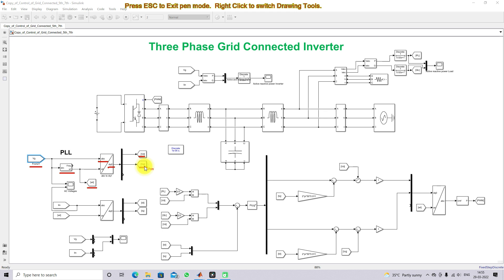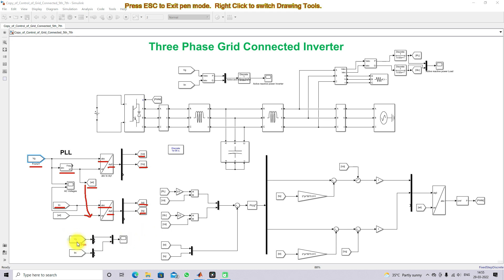Here we are controlling the inverter current. The inverter current is converted into DQ form using ABC-to-DQ transformation, with omega-T taken from the PLL. Finally we have ID and IQ of the inverter current. We also measure single-phase voltage and current to check the phase angle — whether the inverter is supplying real power or reactive power.